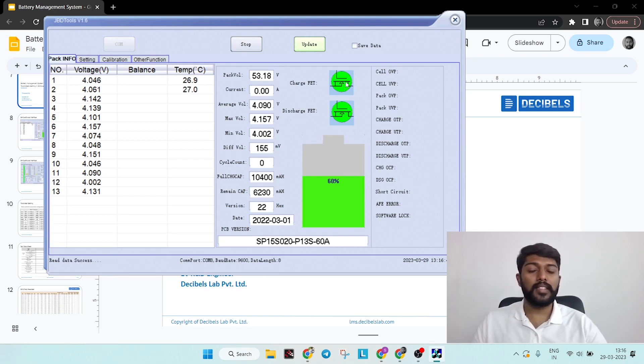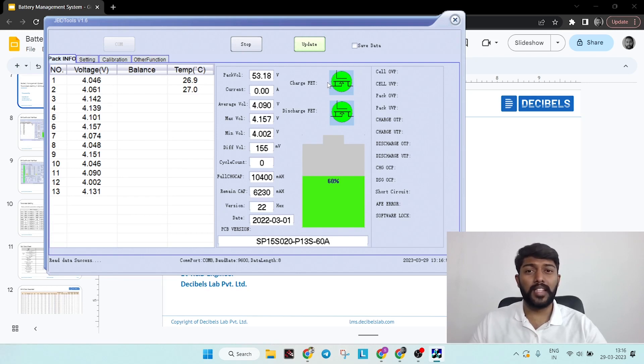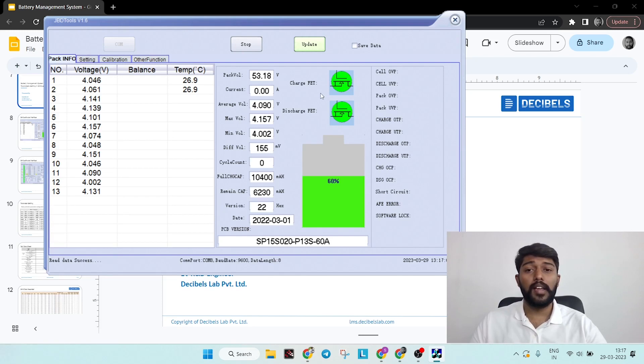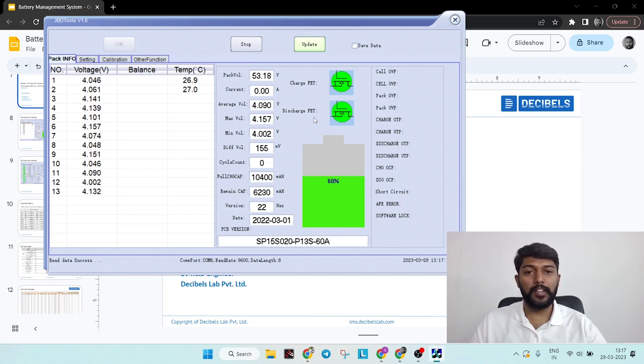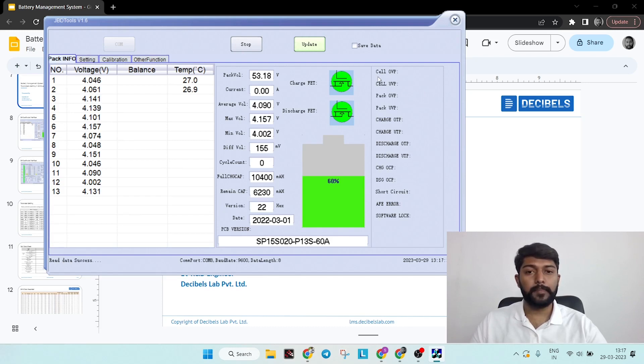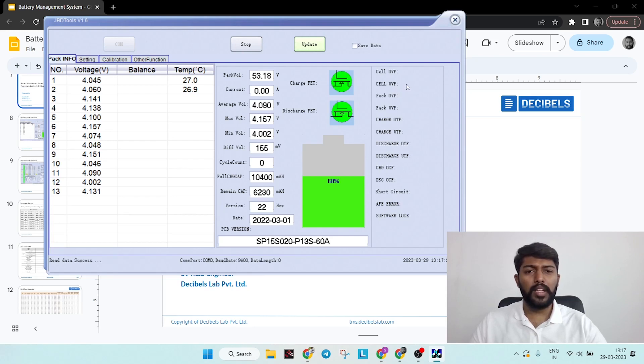It's in green color which shows the MOSFET is in on state. If any malfunction happens, such as cell overvoltage protection or pack overvoltage protection, the MOSFET will turn into gray which indicates the MOSFET is cut off to protect the battery pack. Similarly, it is applied to the discharge. This window is called the warning window - any parameter that has crossed the boundary condition, for example cell overvoltage protection or undervoltage protection, you will have a warning symbol on this window.